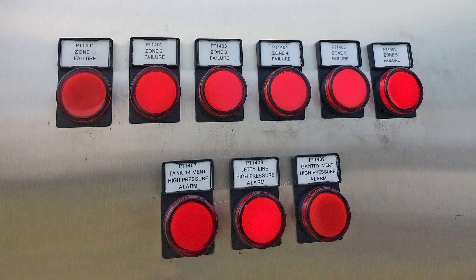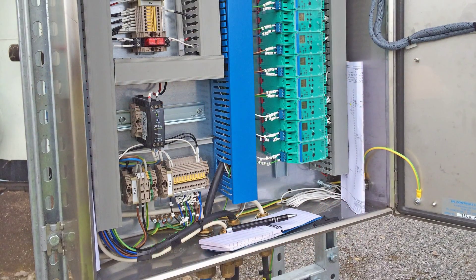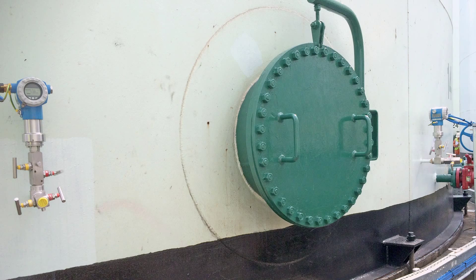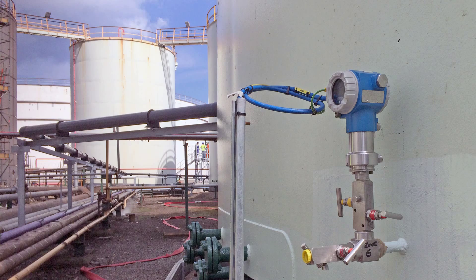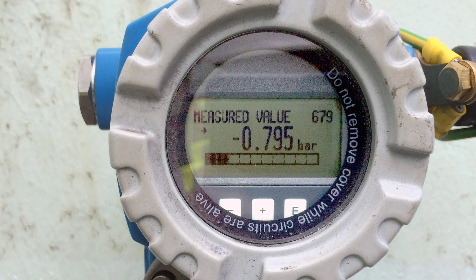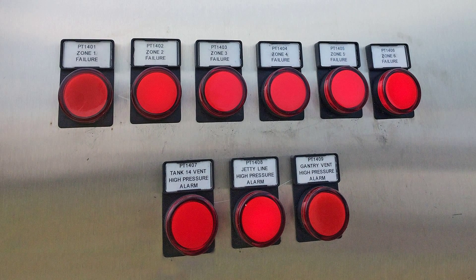The system consisted of six vacuum instrument gauges fitted and configured to monitor four quarter-wall zones plus two zones on the floor area, so that any loss of vacuum could be quickly and easily identified and remedial action taken. Other software package options are available to have the monitoring system accessed remotely from any location worldwide if required. Creating a vacuum between the double layers means that should there be any breach to the double skin liner, internally or externally, the system is triggered by the vacuum pressure loss, instantly alerting the operator well before the possibility of any external pollution.